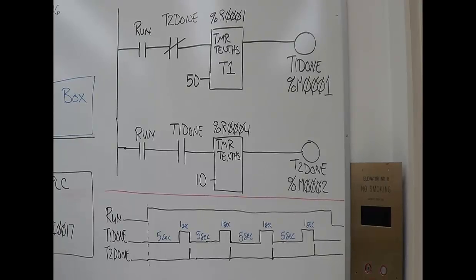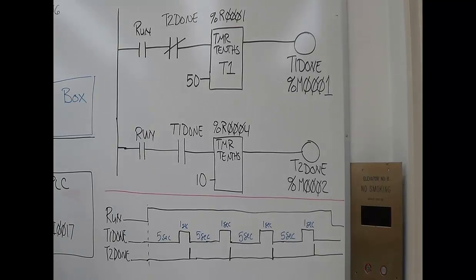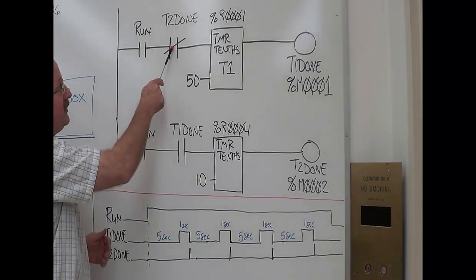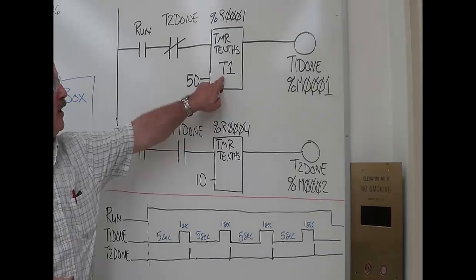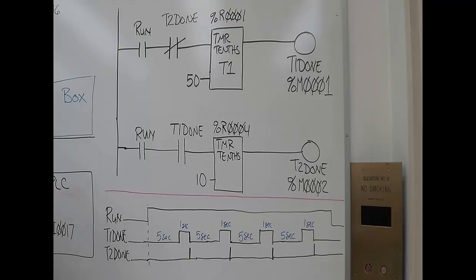When it finishes timing, your timer 2 will go true, turn on, and then this thing will go false and turn off this timer for one scan. It's a one scan reset.